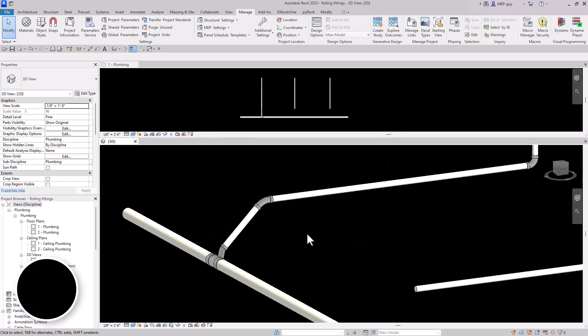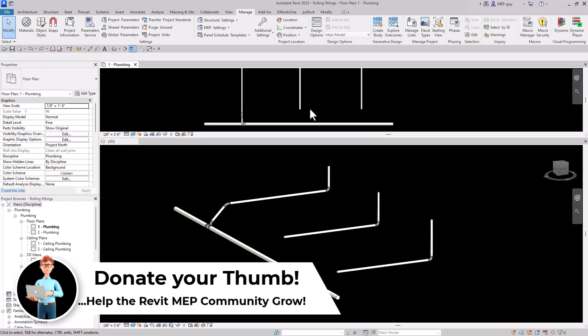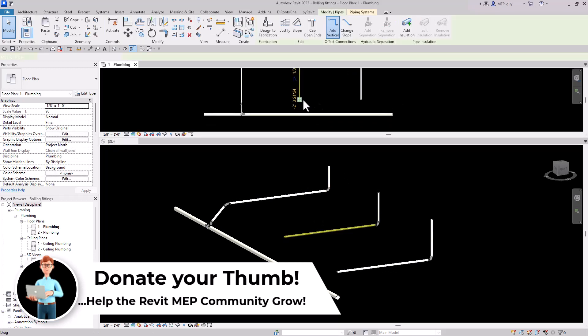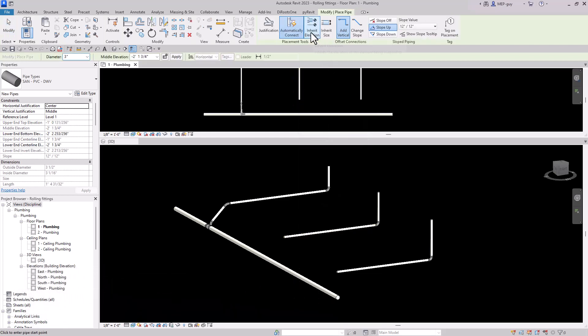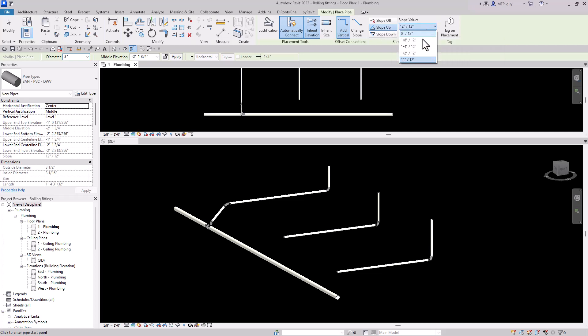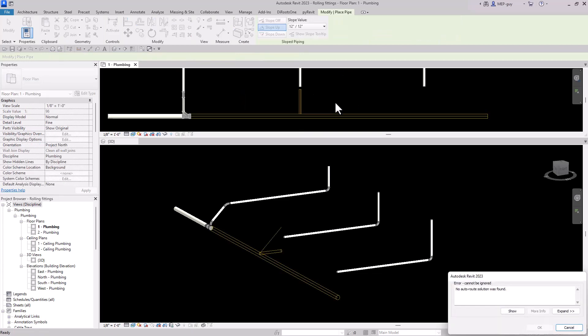Now go into the floor plan and use Create Similar. Make sure 'Inherit Elevation' is selected because we want to inherit the elevation of the main pipe. Also make sure 'Slope Up' is on and the slope value is set to 12 inches per 12 inches. When we try to draw this pipe from one end going up, Revit won't be able to do that — so here's the trick: we have to start from the middle point of our pipe.